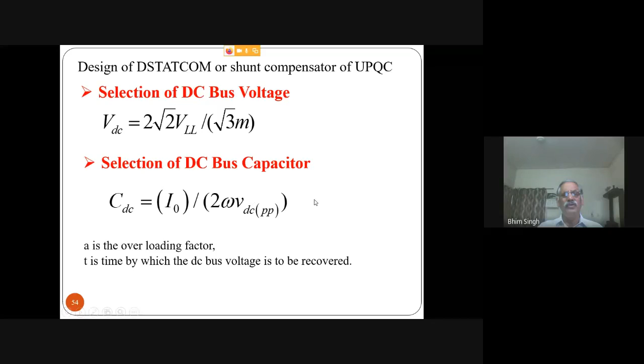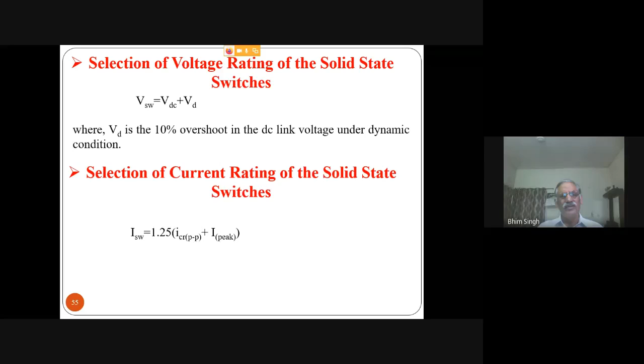If it is single phase, the √3 will go out and it will be only √2 times, so 220 √2 will be 311, and then you bring it to around 360 or 400 volt for single phase. But the DC capacitance calculation we do on the second harmonic ripple, as mentioned here. This kind of relation is valid for many places, like a boost converter or others, and it worked very well for the design calculation.